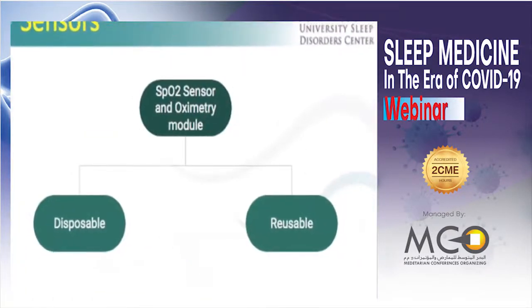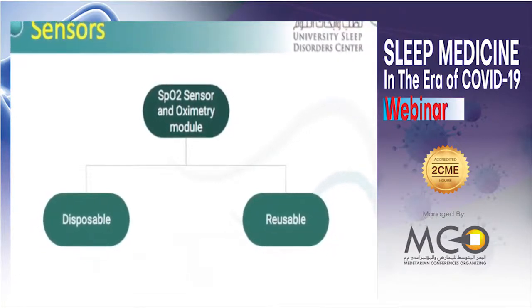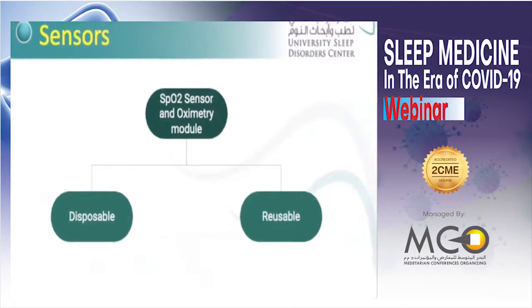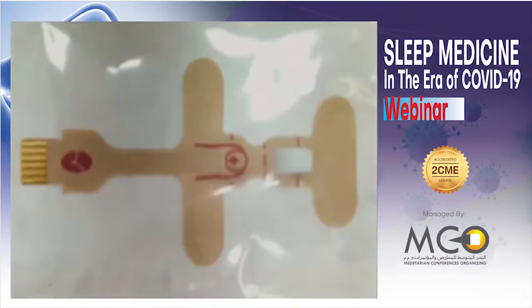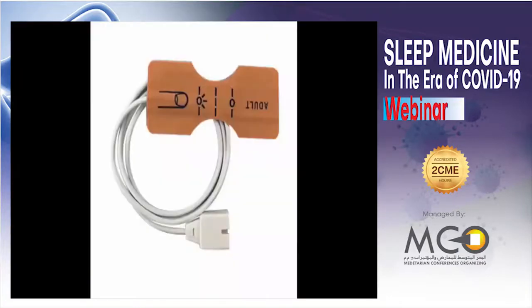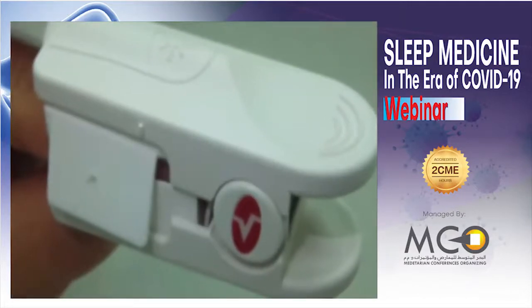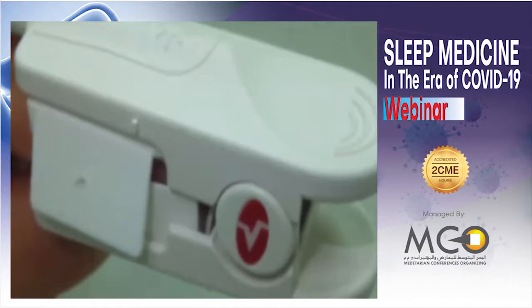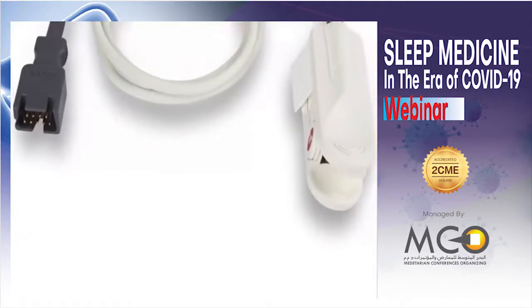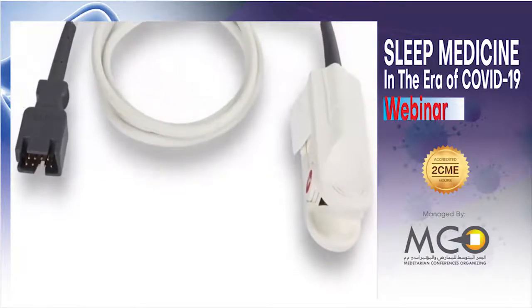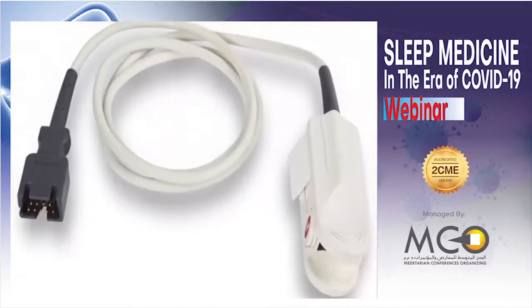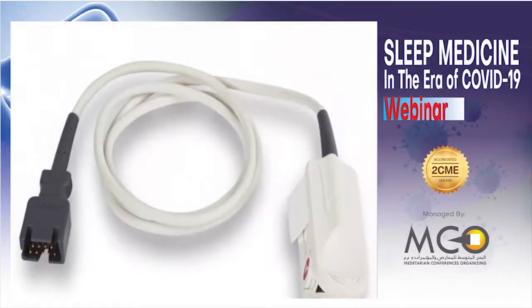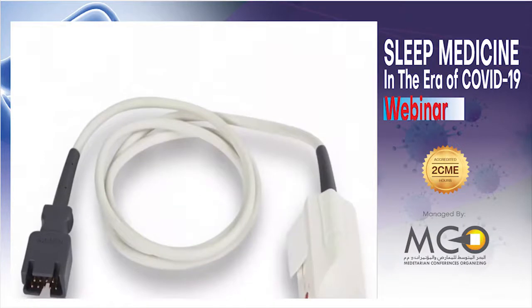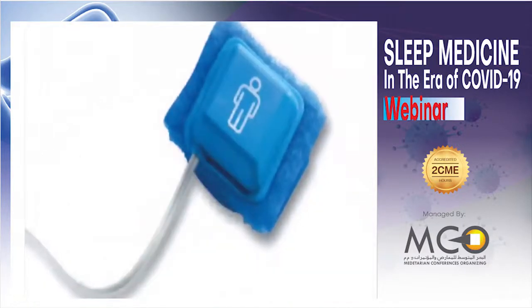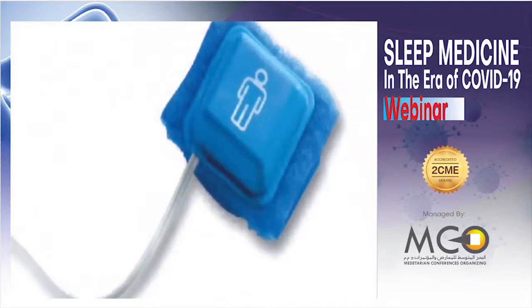Now we will talk about the SpO2 sensor and oximetry. We have two kinds of SpO2 sensor. We have the disposable and reusable. For the disposable SpO2 sensor, it's for single patient use only, so dispose the sensor after the sleep study. For the reusable SpO2 sensors, clean the sensor with a soft wet cloth with a mild detergent or a 10% bleach and 90% water solution. Household bleach contains less than 10% of sodium hypochlorite, so you might need more of that amount with 90% of water.